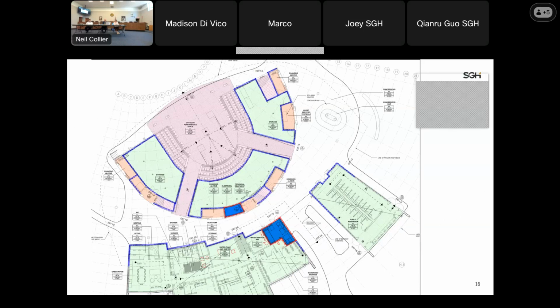So what we've got is everywhere there is an enclosed space, it's sprinklered and separated from whatever is above or beside it that is simply under the shade structure with rated construction. That'll go a long way for property protection. If there's ever going to be a fire at this facility, it's probably going to start in one of these interior spaces, because that's where the fuel load and electrical is present, and that would end up being a sprinkler-suppressed fire, detected fairly early.